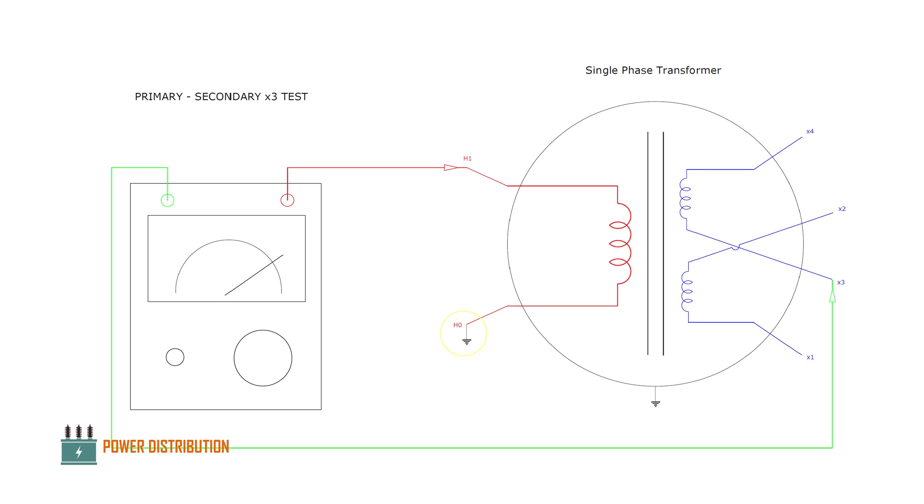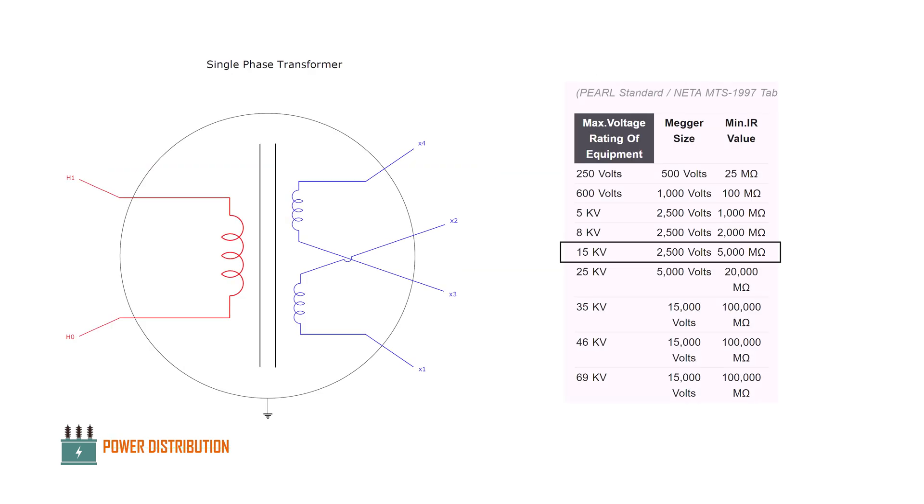Then we measure the resistance between the primary bushing with the second winding on the secondary bushing terminal. In our system voltage we use 20kV line to line, so the phase to ground voltage is around 11.7kV. The minimum insulation resistance should be around 5 gigaohms for this primary winding resistance.